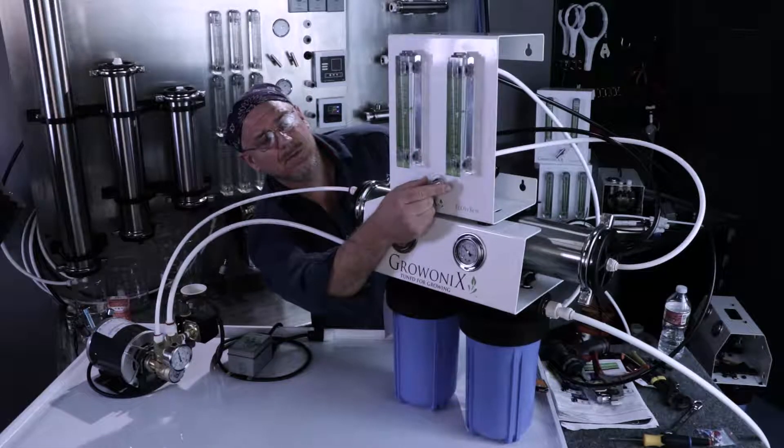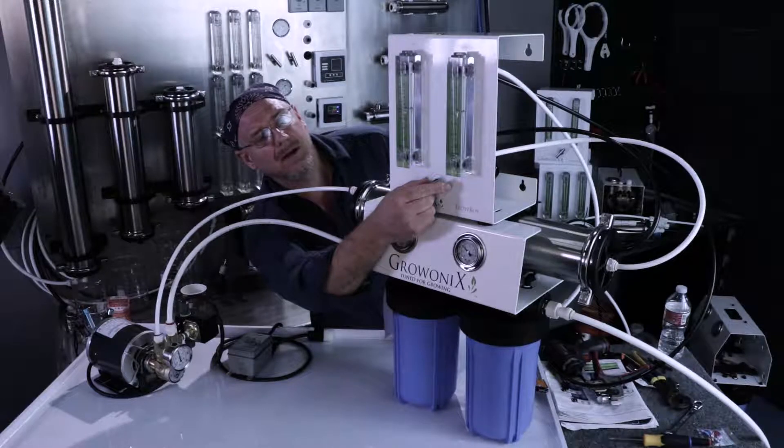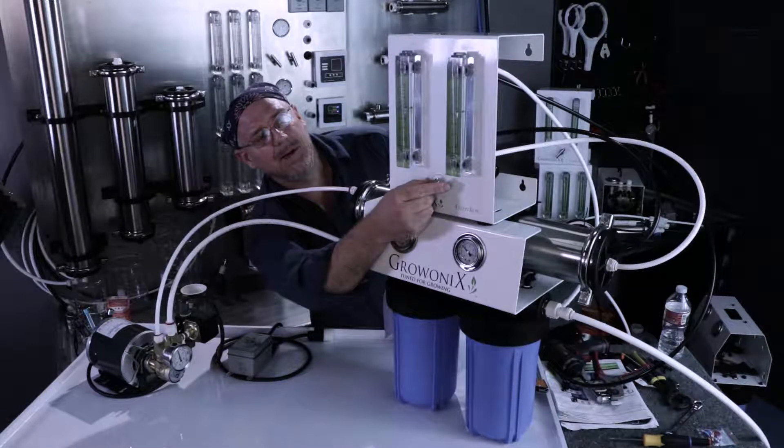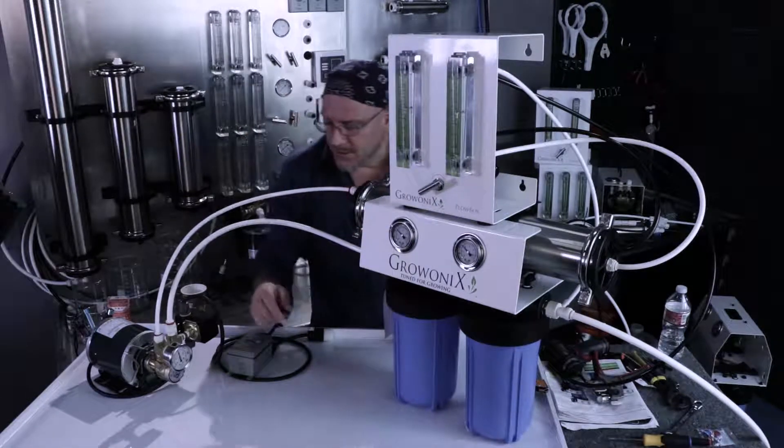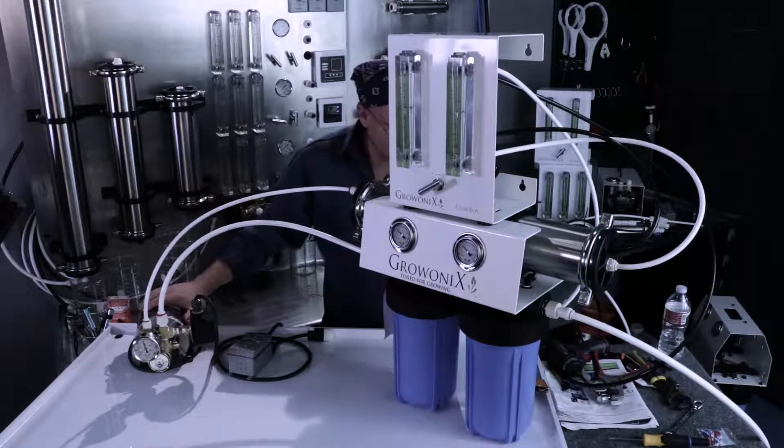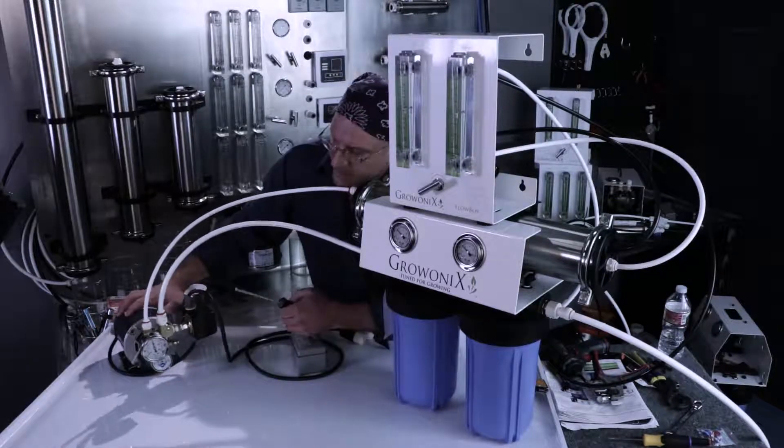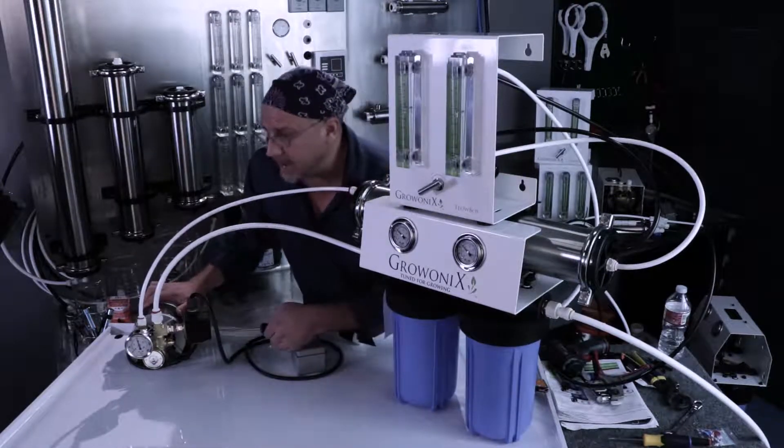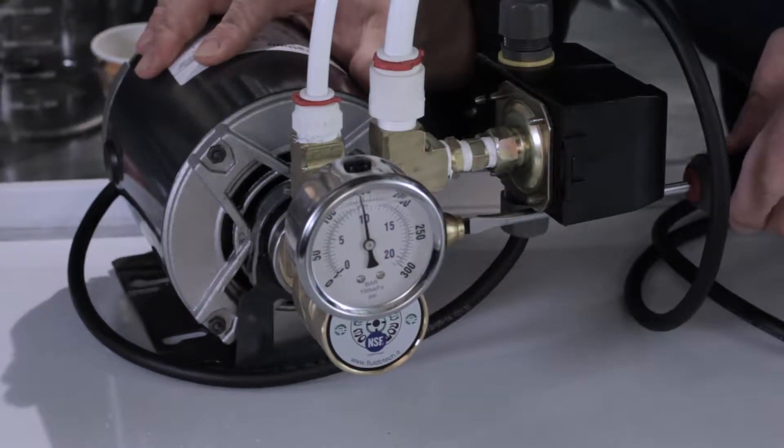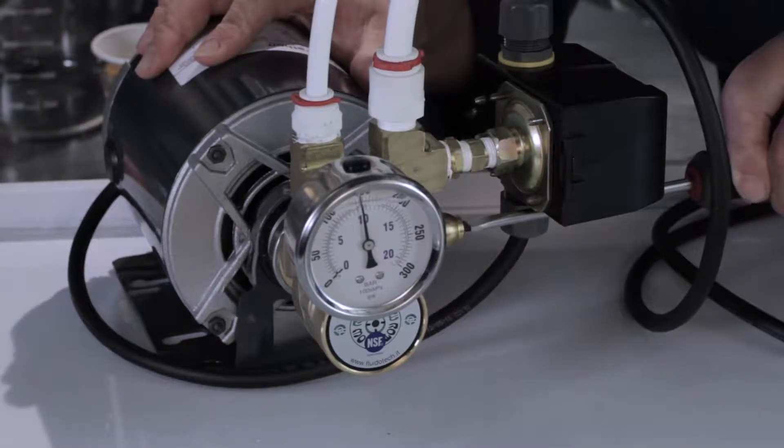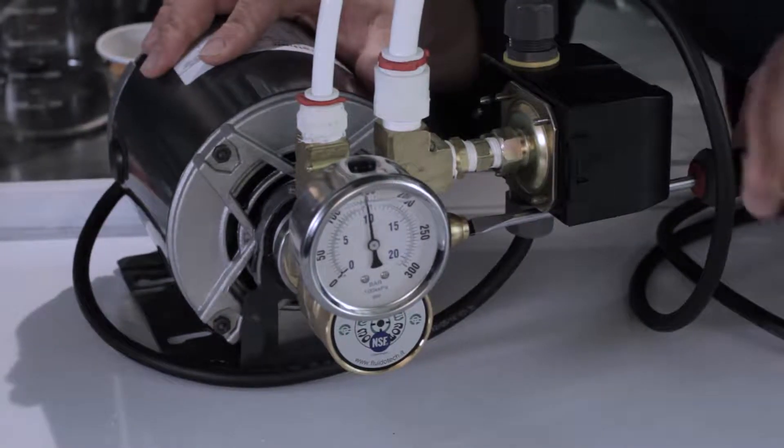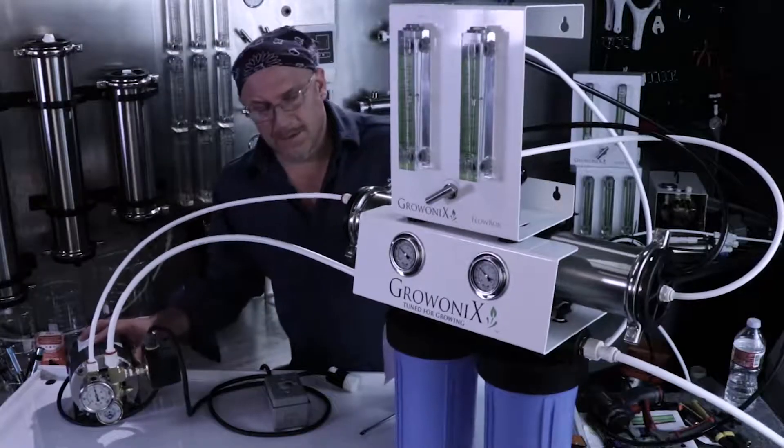Now that we're at a ratio of one to one, I like to run a little more drain water than permeate, so I'm going to open up the drain just a little bit. You'll notice my pump pressure probably changed, so I'm going to take my screwdriver and adjust my pump pressure to 150 psi.